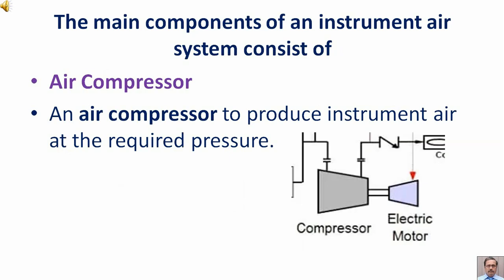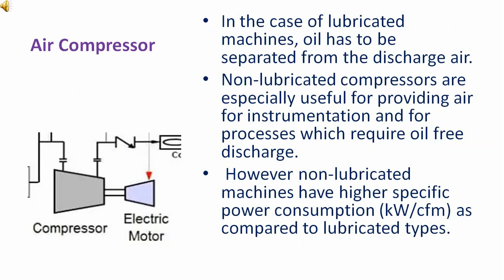Air compressor: An air compressor is required to produce instrument air at the required pressure. In the case of lubricated machines, oil has to be separated from the discharge air. Non-lubricated compressors are especially useful for providing air for instrumentation and for processes which require oil-free discharge. However, non-lubricated machines have higher specific power consumption compared to lubricated types.